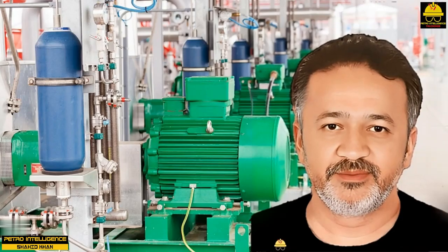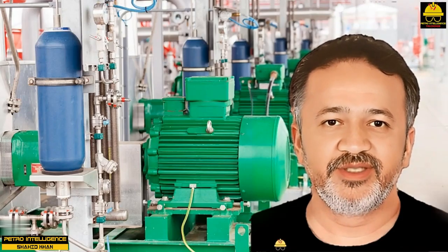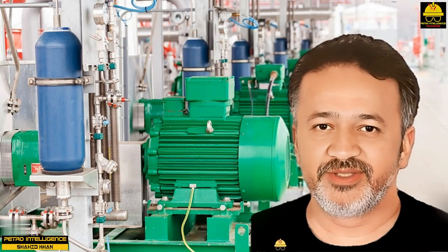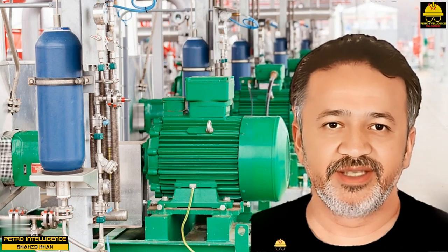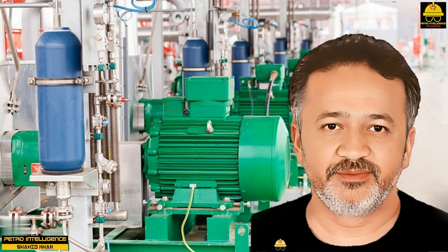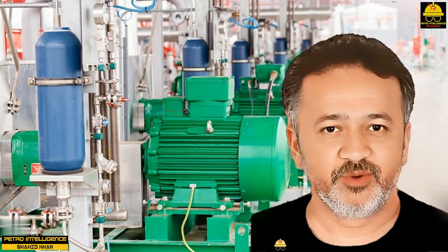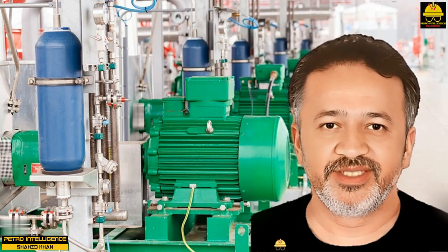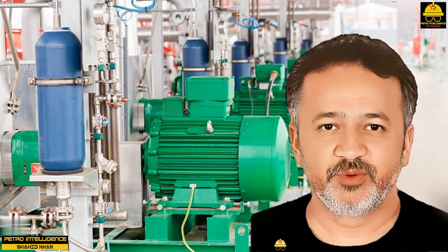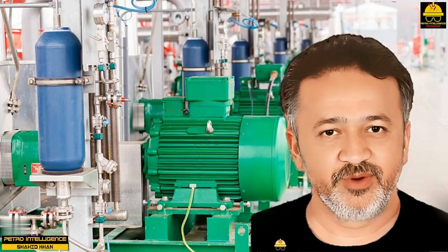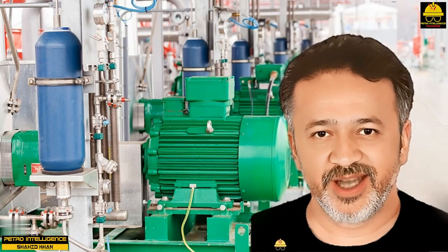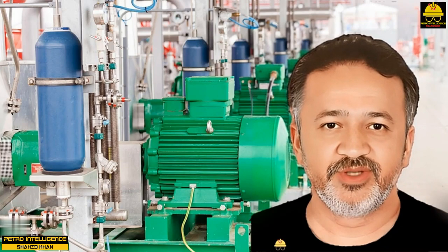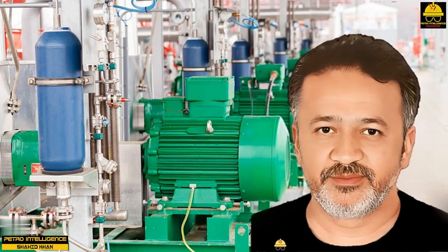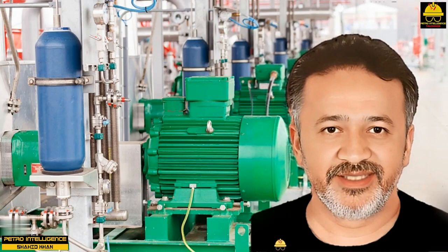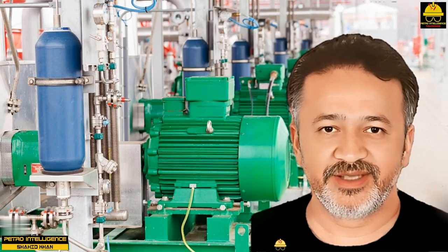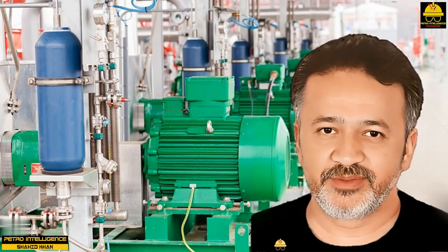Reciprocating pumps. Reciprocating pumps, especially in small volume sizes, are positive displacement pumps very commonly used in the petrochemical industry. Reciprocating pumps are engineered to transfer small volumes of liquid at relatively high pressures. Most reciprocating pumps are self-priming and are operated at relatively low speeds because of the back-and-forth motion and the effects of inertia on internal components. Reciprocating pumps can deliver consistently high volumetric efficiencies even when applied to a variety of fluid types.